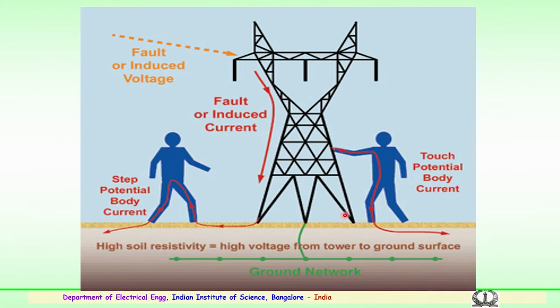Similarly, there could be a touch potential where a tower, metal object, or any other object has fault-induced current flowing to earth. If a person touches the metal object or a tree in such instances, he could experience touch potential, with his body providing the path for grounding. So it could take the path through his body and later be grounded. Proper grounding of equipment is necessary, as such hazards are likely to happen.